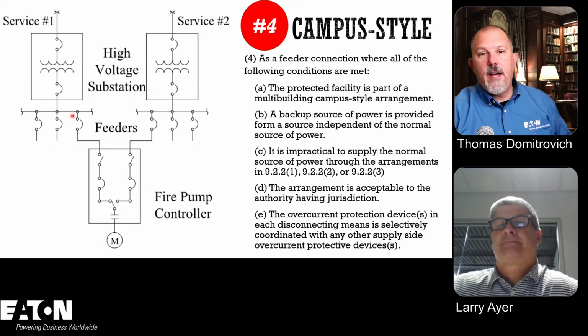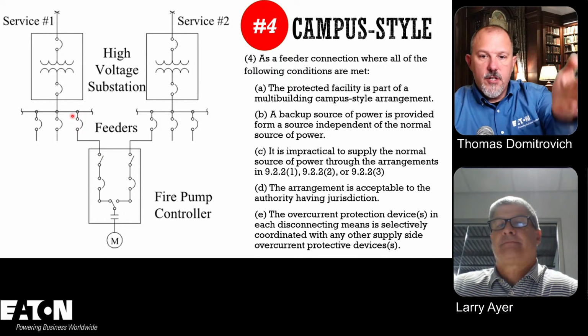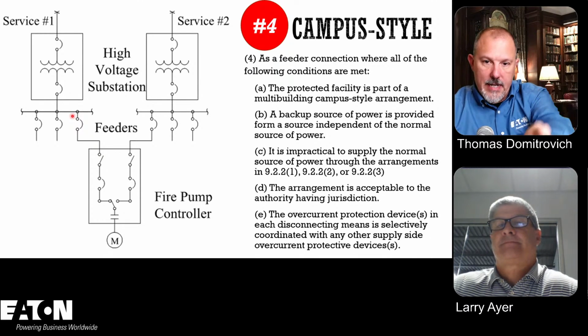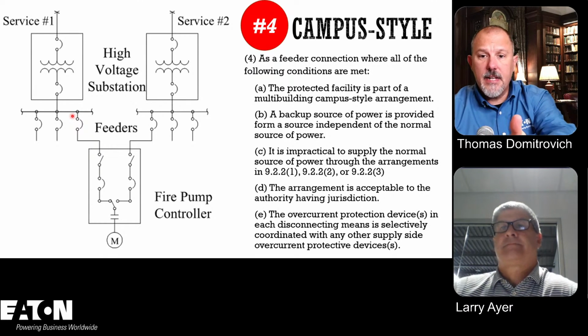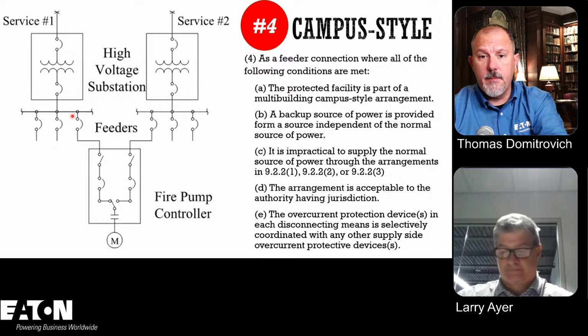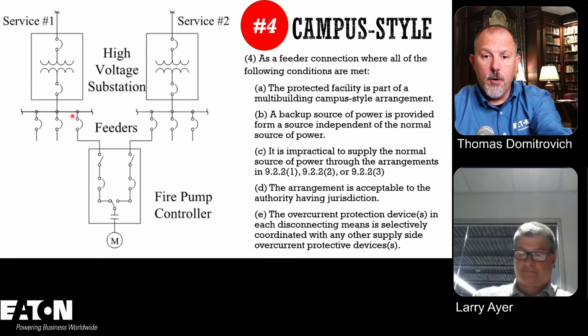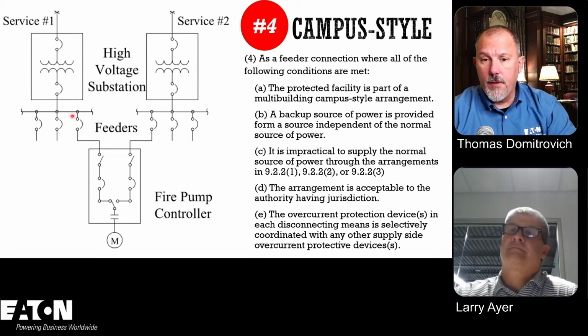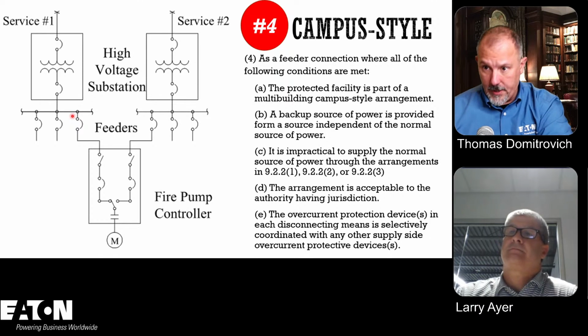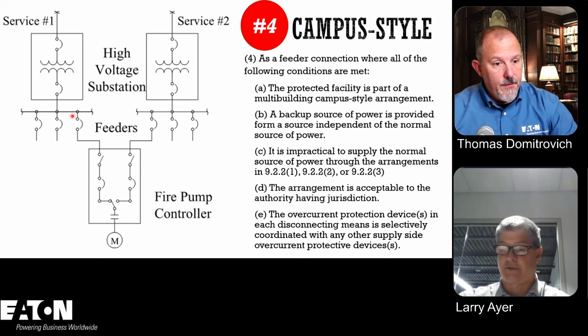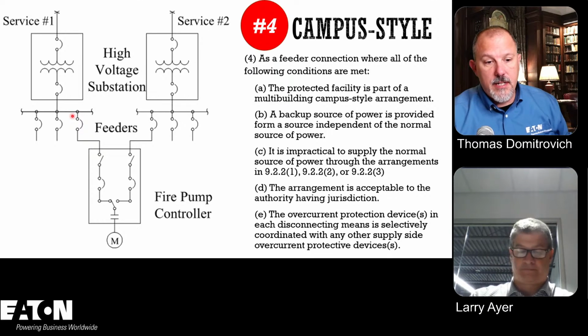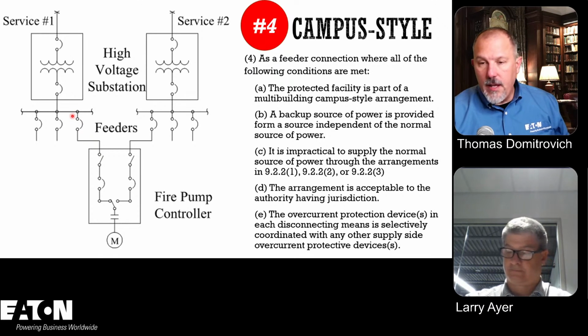Now you could have a direct service feed going down to that fire pump, and then come off of the Article 700 system as a backup for that fire pump as an alternate source, right? That's correct. You could do that. And Felix had a question. He says, are there special requirements for the diesel generator if it is the only power source for a fire pump?